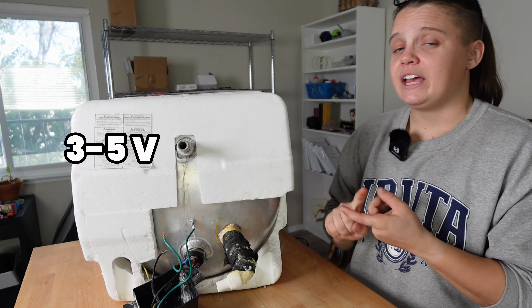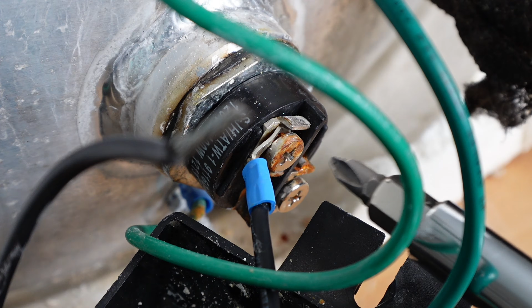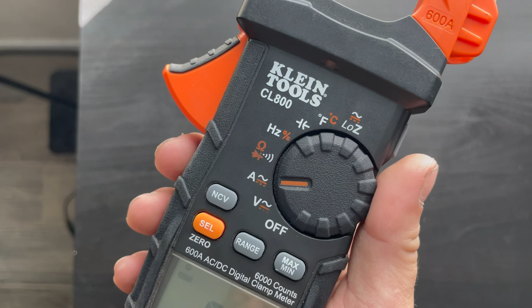If you're getting 120 volts to one side of the heating element and on the other side, the number hasn't drastically reduced, again, it should be like 3 to 5 volts, then this heating element is most likely your problem. The way you can double check is go throw that breaker again, so we're not sending AC voltage to the water heater at all. We're then going to unscrew the 2 connections and disconnect the wires going to the heating element.